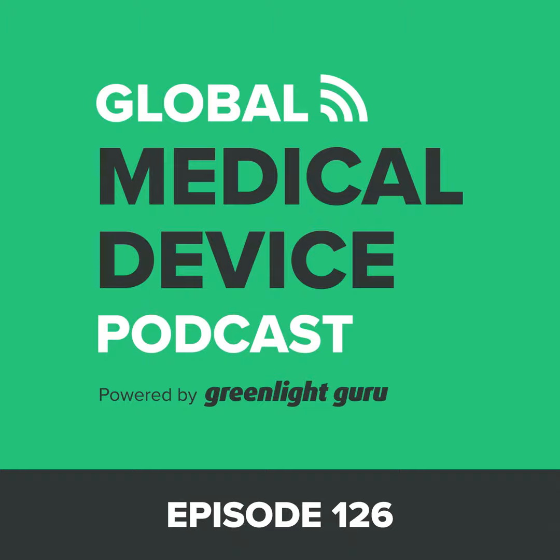You should be considering all of those methods, without getting too much into the engineering detail here. It's going to be contingent on the device, both the material of the device as well as the geometry of the device. For example, if you have a very long catheter and you use a sterilization method where the sterilization substance cannot penetrate the wall of the catheter, then how do you ensure that substance is going to get all the way through the length of the catheter? In other words, it's only going to diffuse a certain distance, and so you might actually have to help it. You might actually have to blow it through. So bottom line, you have to consider the geometric parameters. You have to consider the material parameters. Some materials are more conducive to certain methods of sterilization than others.